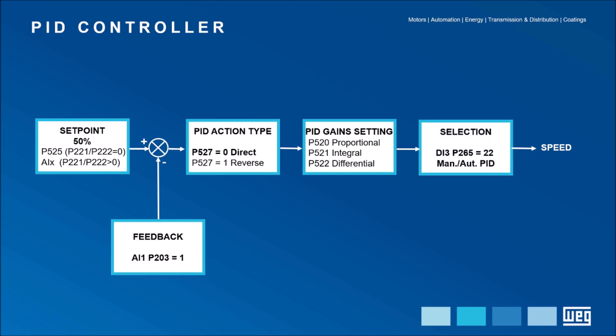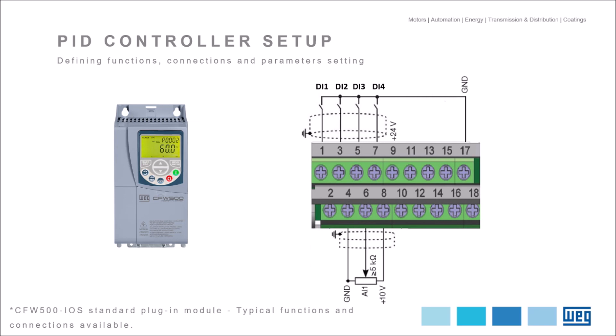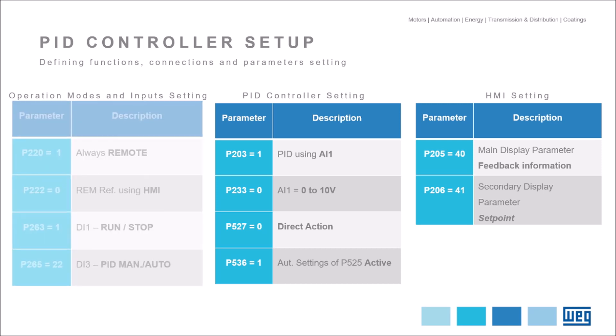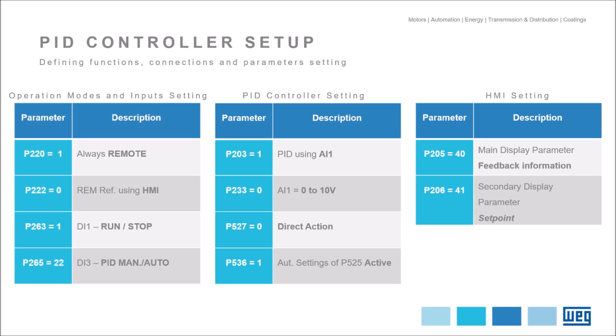In the final step, DI3 was set for manual-automatic, which enables motor speed control. Keep in mind that motor speed variation is what keeps the process variable constant. This was the control connection used in our example, where DI1 was run-stop and DI3 was manual-automatic. The pressure transducer was simulated by the analog potentiometer connected to analog input AI1. You can see here a list of the parameters set in the example — those related to the mode of operation and inputs, those related to the PID regulator, and finally the HMI parameters.